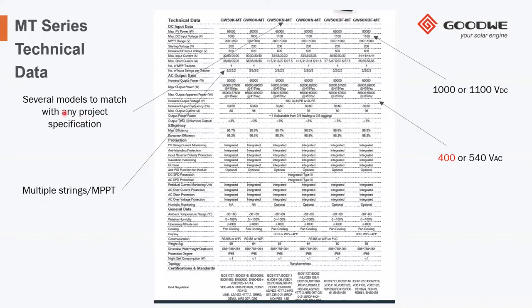We have a very wide range of product within the MT series to match with any project specification. You see, we have 50K, 60K, the N version, the BF version, and so on. And this is very important. It's a class of inverter which is very flexible, can match any requirement for any specific project you can have. As an example, you can have the input on the DC side at 1000 or 1100 volt, or you can have the output on the AC side at 400 or 540 volts.